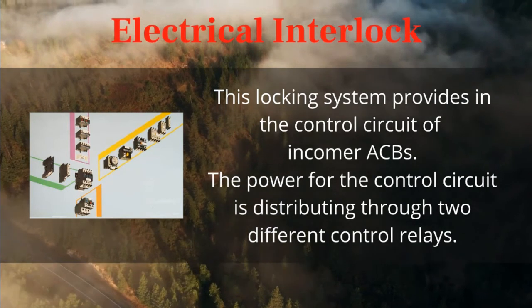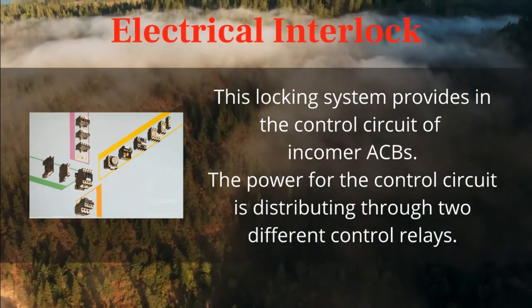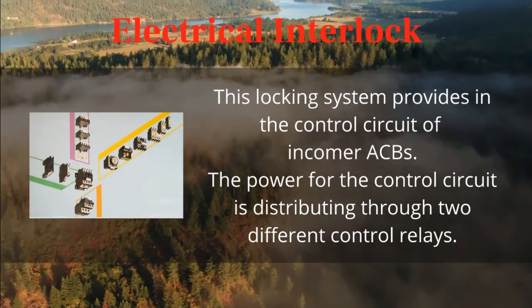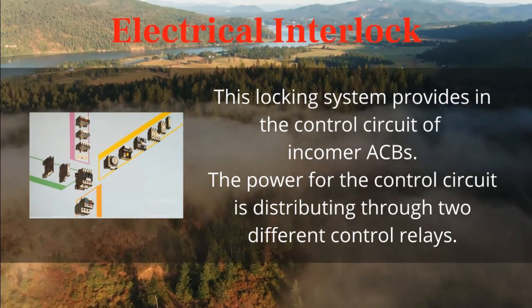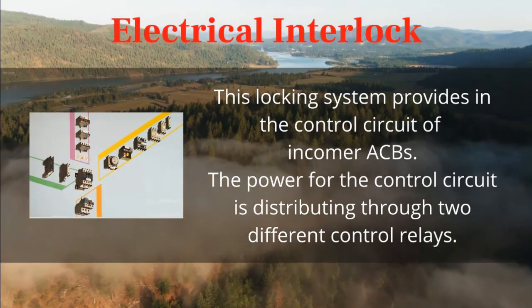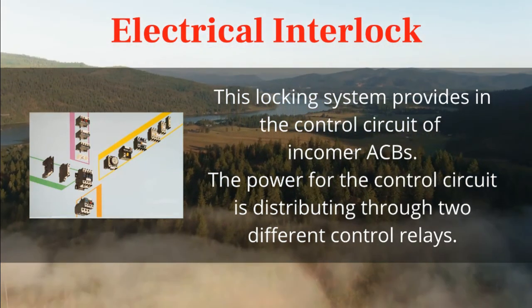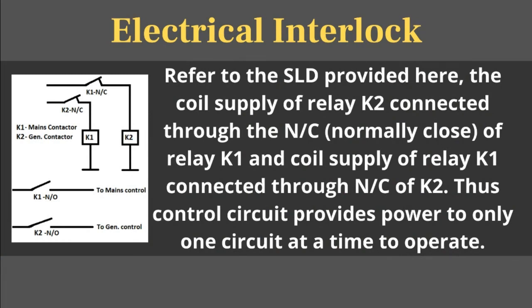Electrical interlock is provided in the control circuit of the incomer ACB. The power for the control circuit is distributed through two different control relays. The coil supply of relay K2 is connected through the NC (normally closed) contact of relay K1, and the coil supply of relay K1 is connected through the NC of K2. Thus the control circuit provides power to only one circuit to operate at a time.